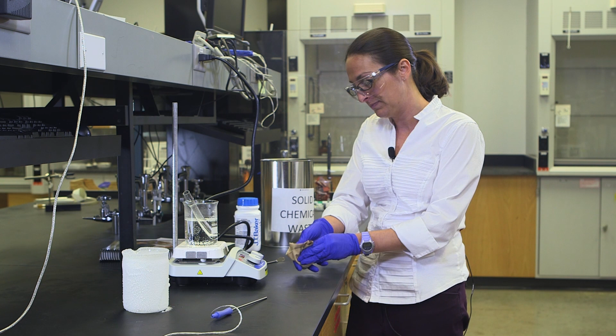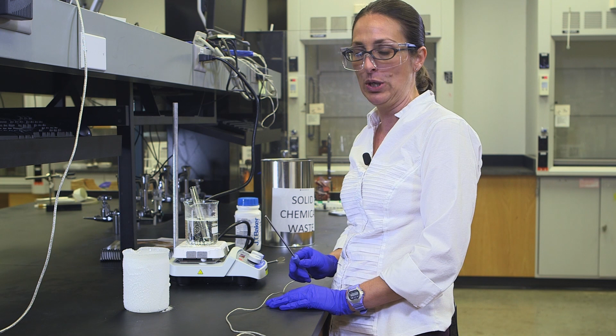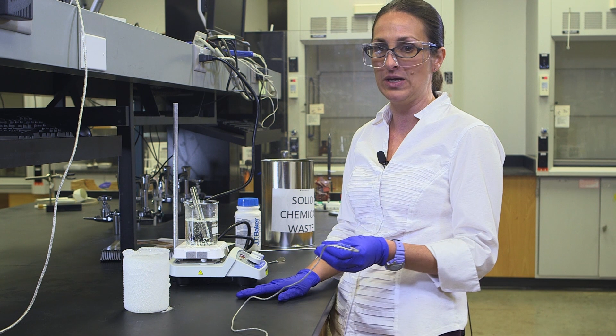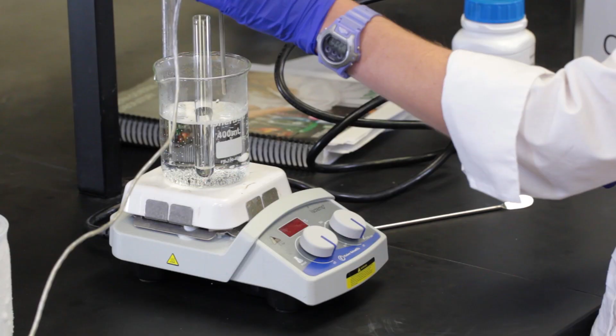melt that. Before you start using the Pasco probe system, the temperature probe, you're going to calibrate it. This is a dry ice acetone bath. We're not going to put a thermometer or a temperature probe in that. It's too cold. So we'll have an ice water bath, and we will just calibrate the system to 0 in an ice water bath.